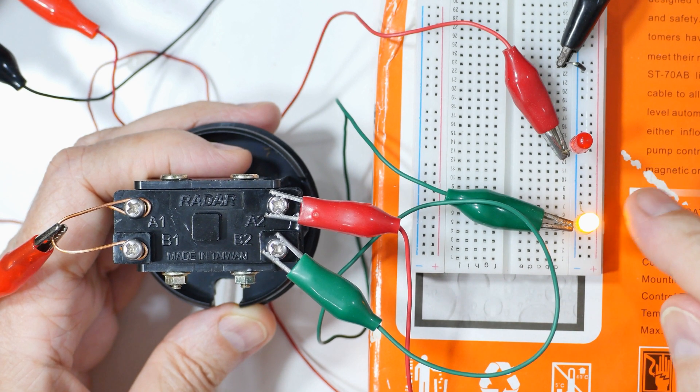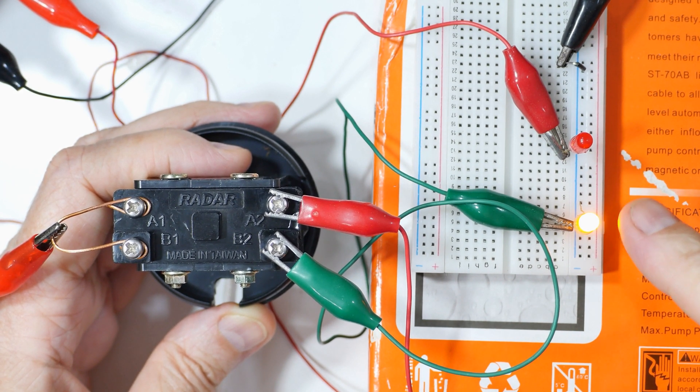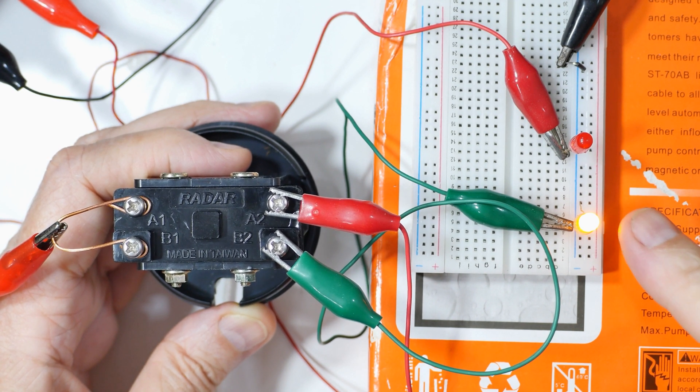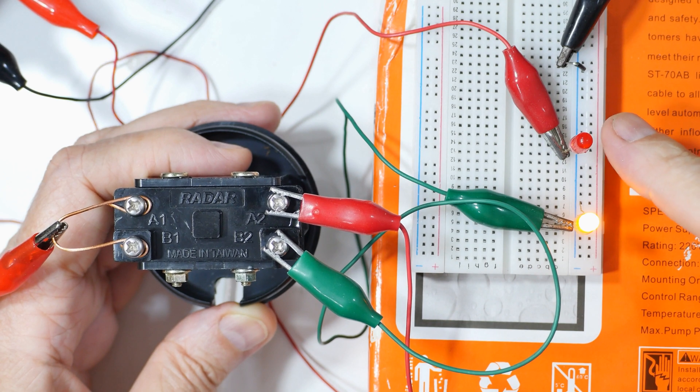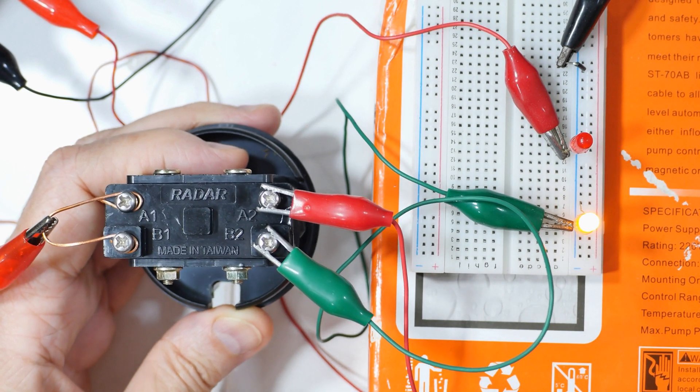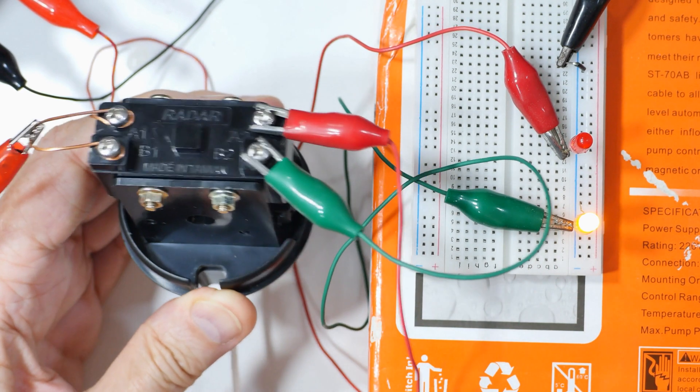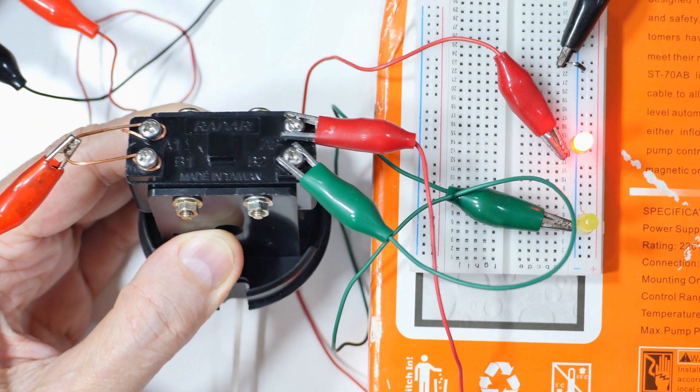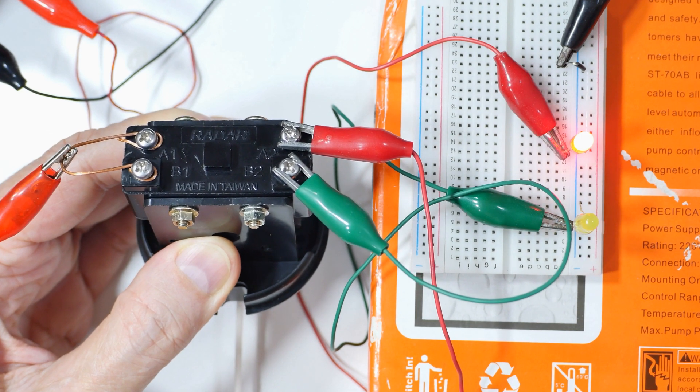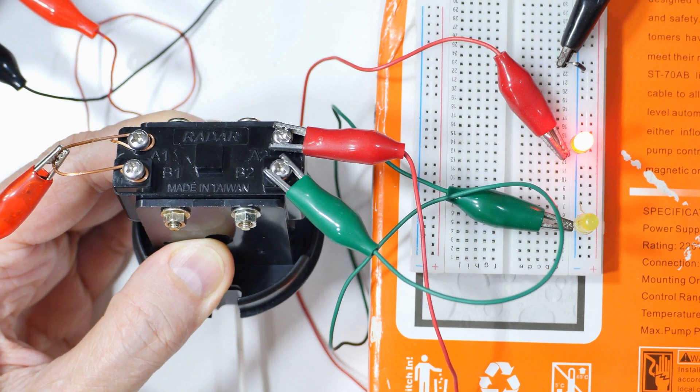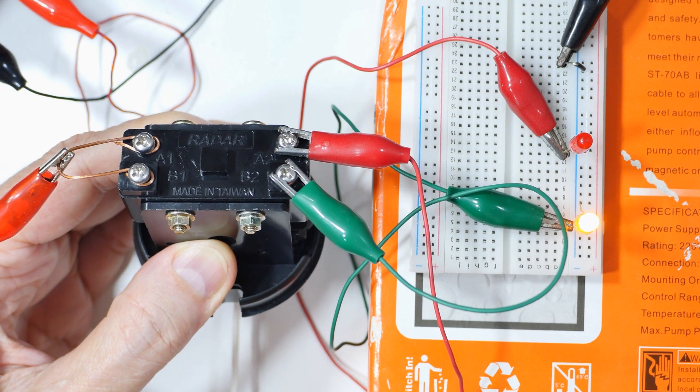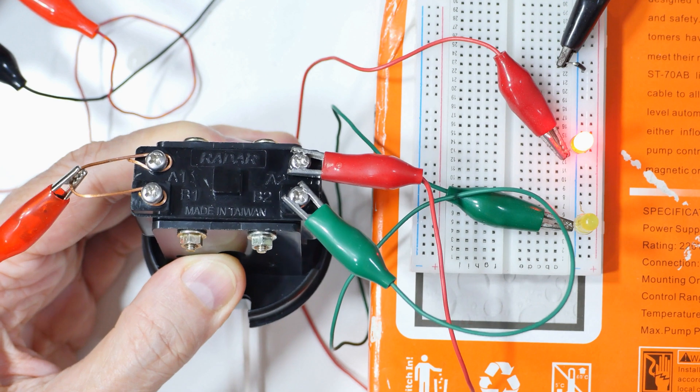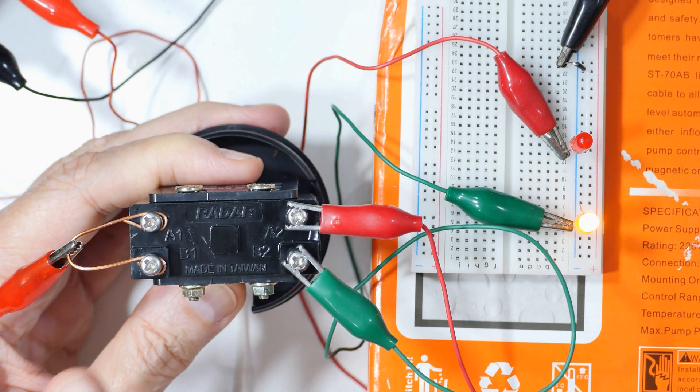In our situation, when the tank is full, this would be the indicator light telling me the tank is full, and this would be when the pump is running. Let me pull on the string which is down here below. I'll get my thumb out of the way so you can see what happens. This would be the pump running, and then when the tank's full and the floats come up, it goes click and I get an indicator that the tank is now full. Just normally closed and normally open positions.